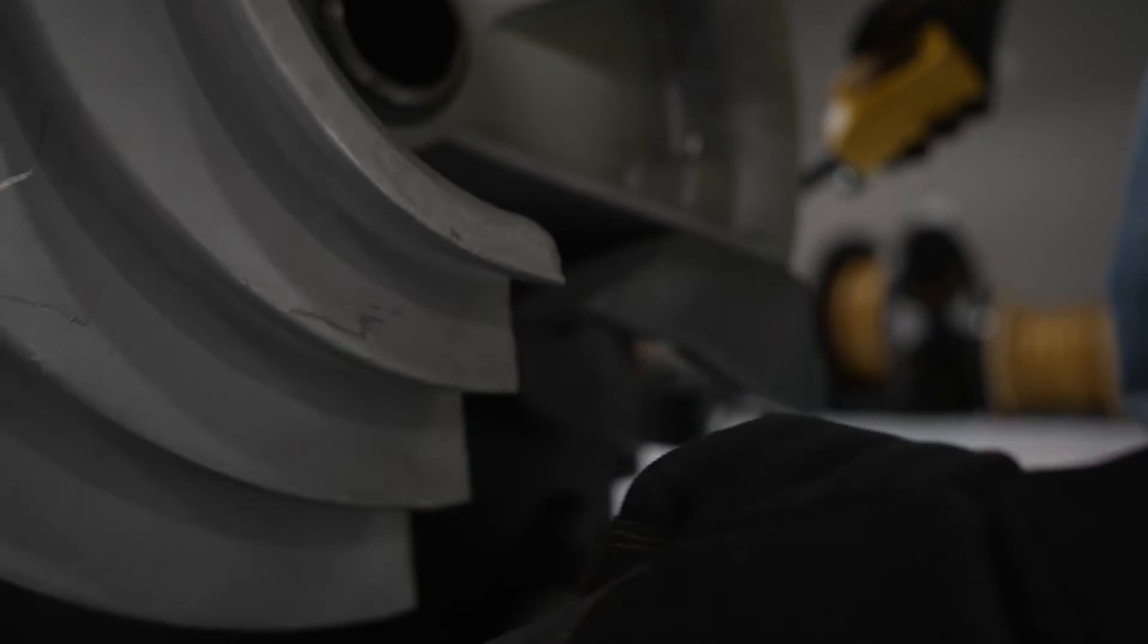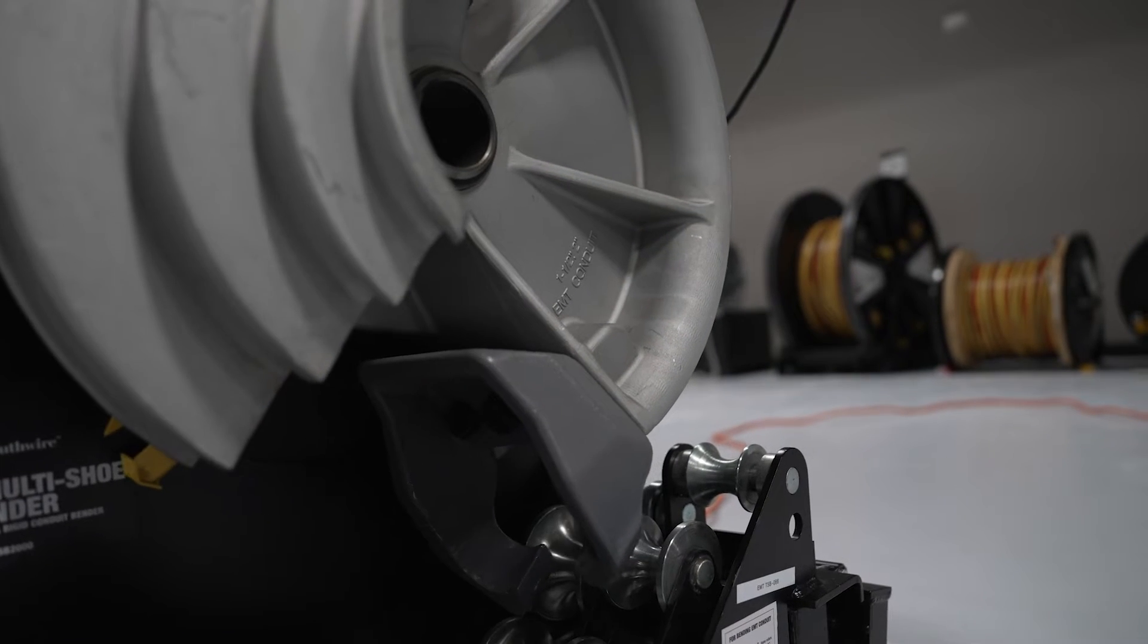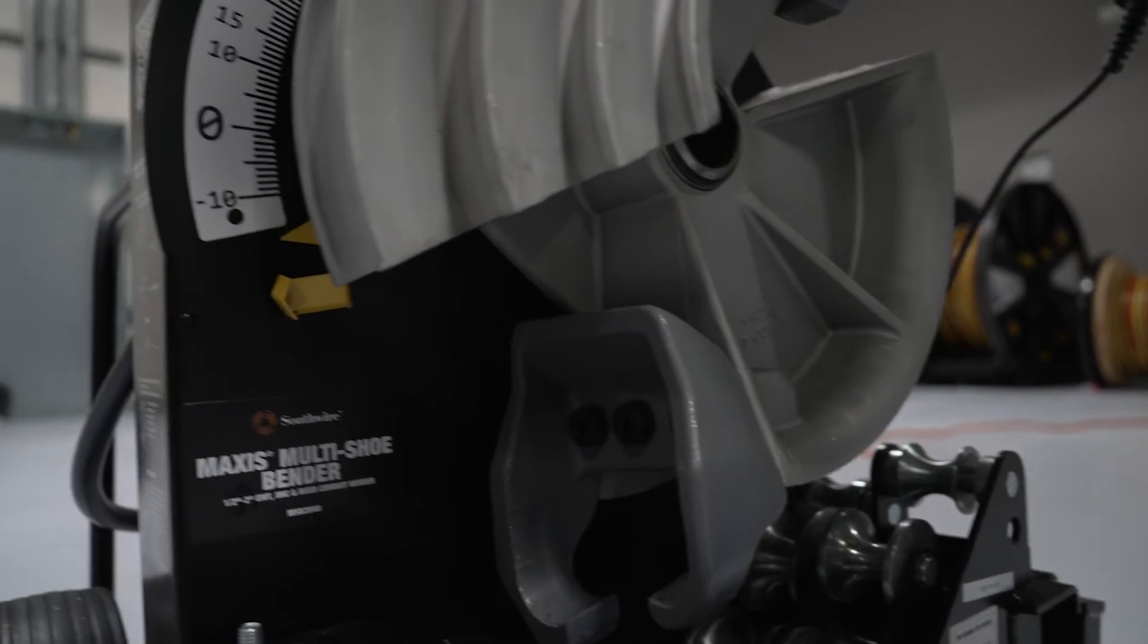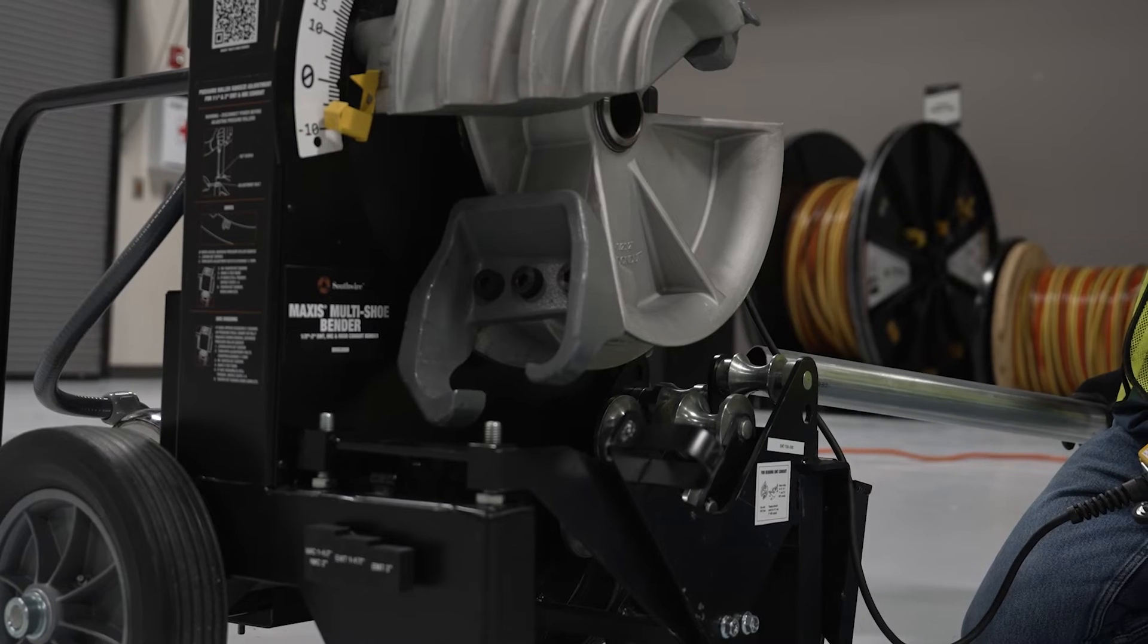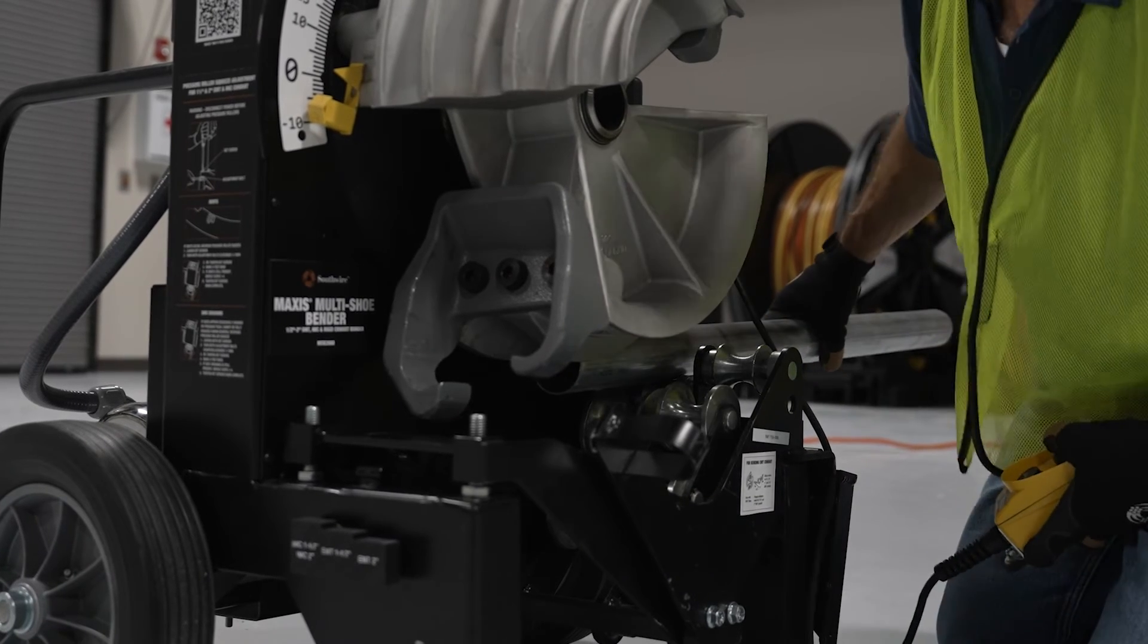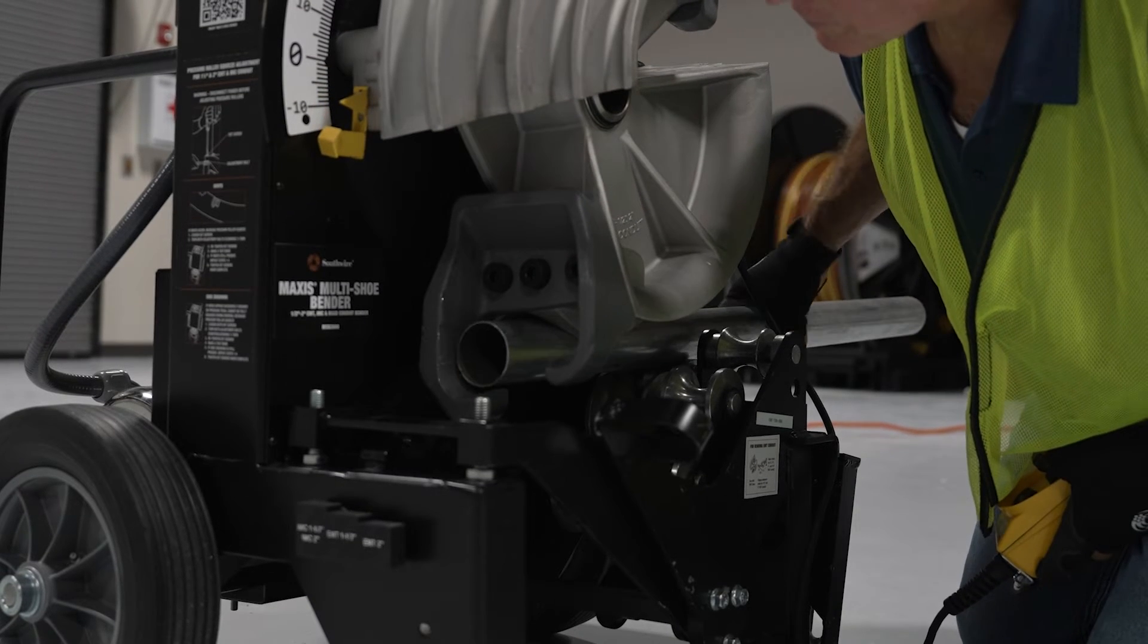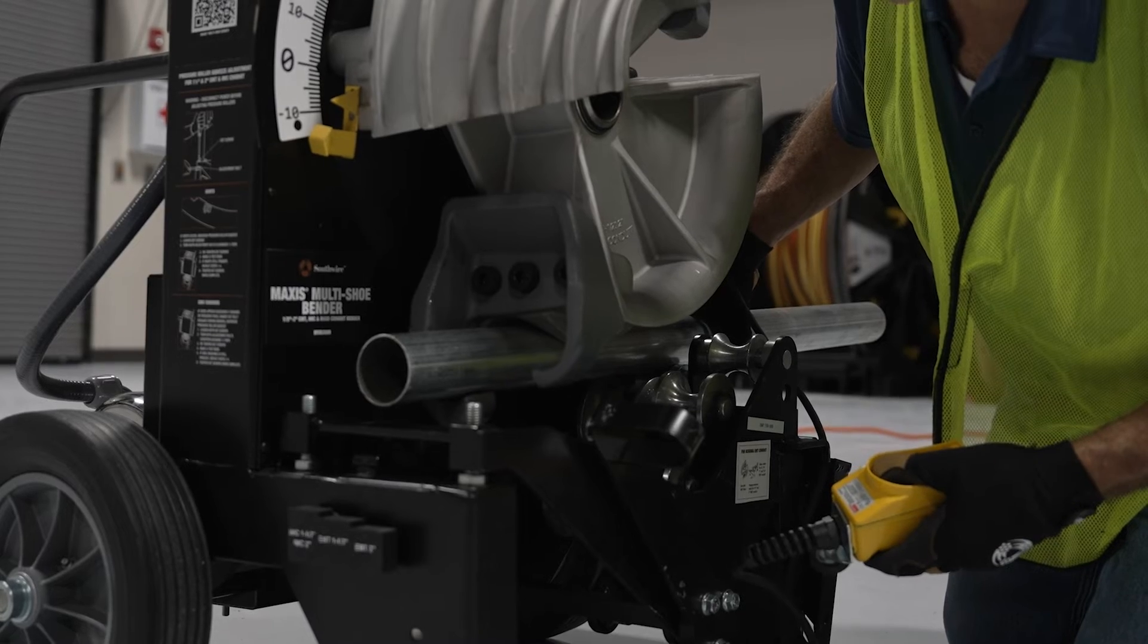Now using the pendant, press forward to rotate the shoe clockwise. Rotate the shoe until the inch and a half and two-inch half of the shoe is facing down and the arrow pointer is approximately five degrees before the zero degree starting point. Then, facing the front of the bender, load the conduit into the right side of the bender. Guide the conduit into the bender until it rests in the hook, and you may need to rotate the shoe a little bit so the conduit lies in the hook.